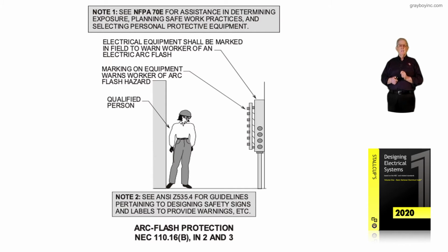Now, when that math is performed, we take the square root of the total, and the distance for a curable burn is 2.21 feet, or anything beyond that, like 3 foot, 4 foot. But anything closer to the energized components than 2.21 foot, then it wouldn't be a curable burn. It might be a third degree or higher degree burn.